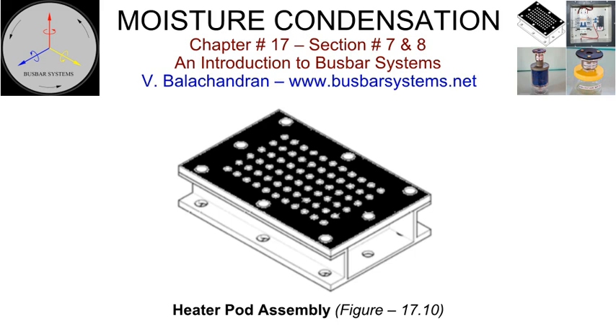Heater covers and fins are susceptible to corrosion since they operate under elevated temperatures. The material of the outer casing may be specified for the specific project. To maintain the desired temperature of the air inside the enclosure, heater pods are provided at strategic locations along the route. Heaters are also accommodated as close to the insulators and bushings as possible.